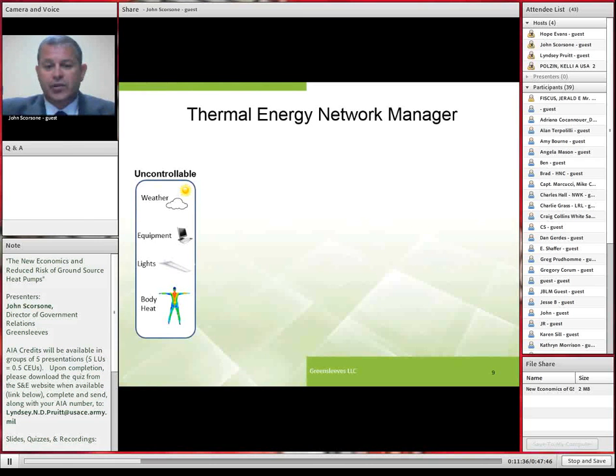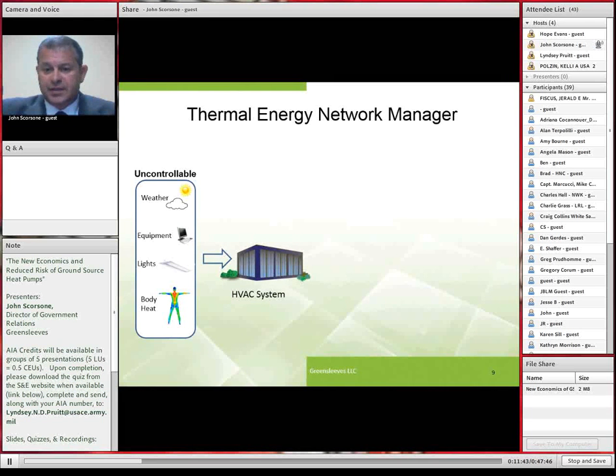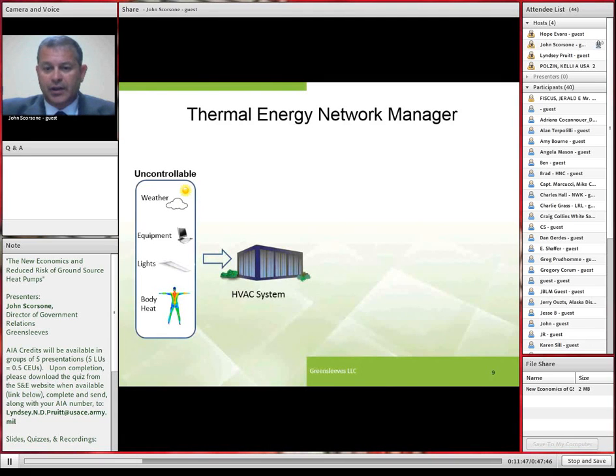As the demand is created, it responds to move heat where it needs to. You can switch to a ground source heat pump system, and now you just have a bore field in the equation that is also reactionary. You only get the amount of heat that you can put in the ground to make the system work. So all is well, provided you don't run out of additional space in the ground to store the extra heat.